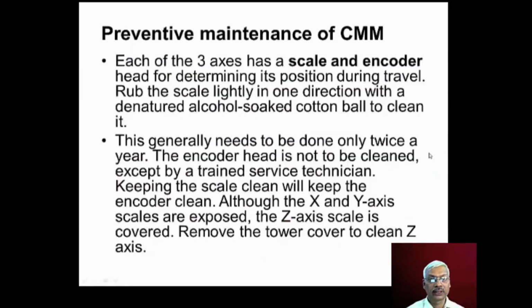Now let us discuss how we can carry out preventive maintenance on coordinate measuring machines. Each of the 3 axes of CMM has a scale and encoder head for determining its position during travel. We should rub the scale lightly in one direction with a denatured alcohol soaked cotton ball to clean the scale. This generally needs to be done only twice in a year. The encoder head is not to be cleaned except by a trained service technician. So keeping the scale clean will keep the encoder clean.